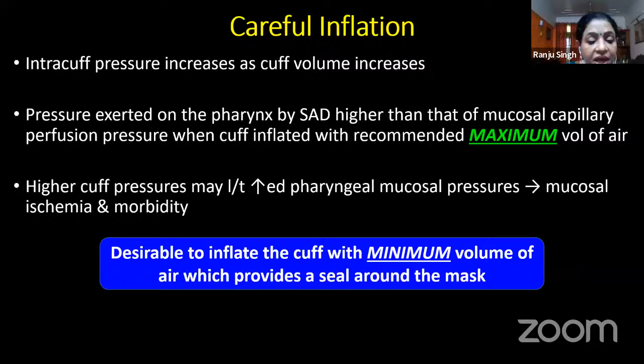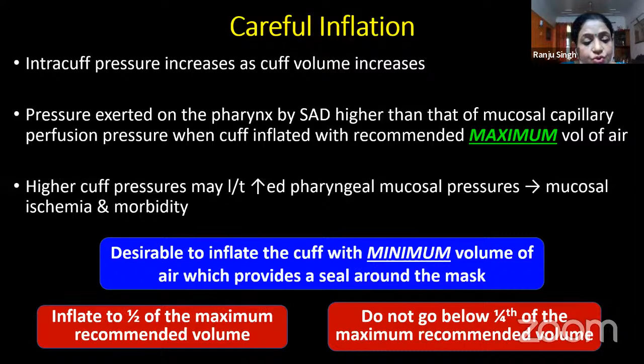Inflate to half the maximum recommended volume, but do not go below 1/4 the recommended volume. So after the device has been pushed in place, do not touch the airway tube. Gently inflate the cuff with some amount of air, which should be, to start with, the minimum amount of air that can provide an effective seal. This is usually half the maximum volume that is recommended. Every device has a defined maximum volume of air that can be put for a particular size.